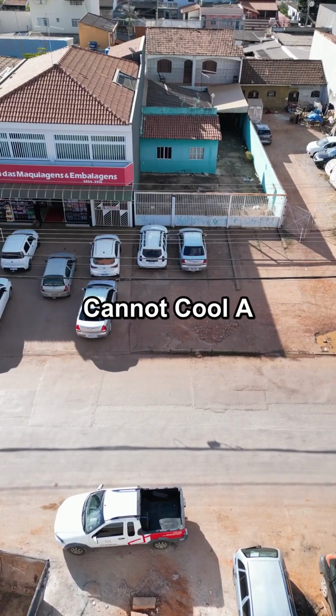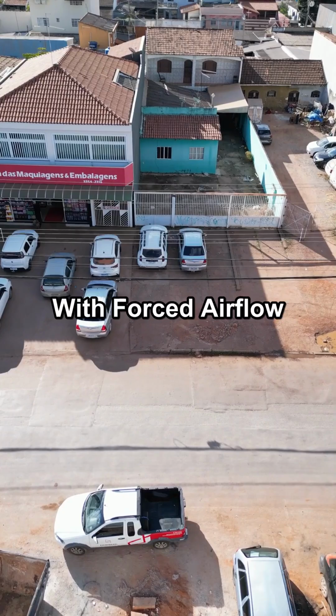You cannot cool a 200 kilowatt rack with air. The physics simply does not support it. The heat flux density through the cabinet face is too high to extract with forced airflow at any commercially practical velocity.